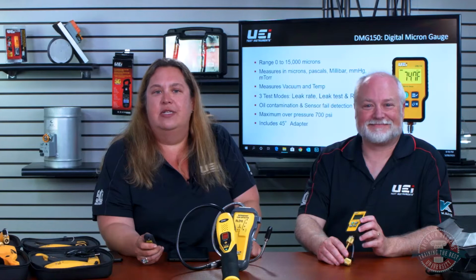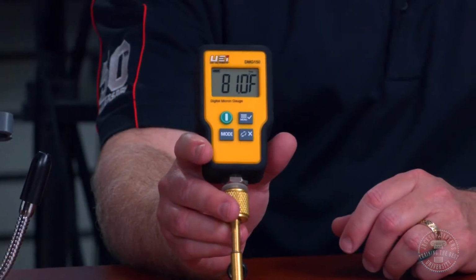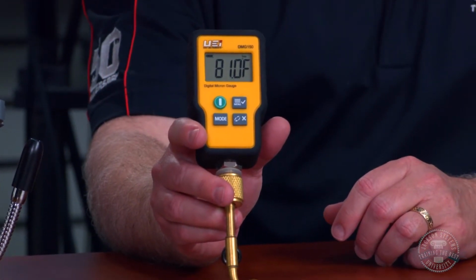But what's really nice about this Micron Gauge is it has a range that's from 0 to 15,000 microns. It has several scales that you're able to scroll through. It'll also measure your vacuum and your temperature. It has 3 modes that you're able to go through. So you can see your leak rate, leak test, and run mode. But honestly, one of my favorite features on there is that it has an oil contamination and sensor fail, which is really nice.